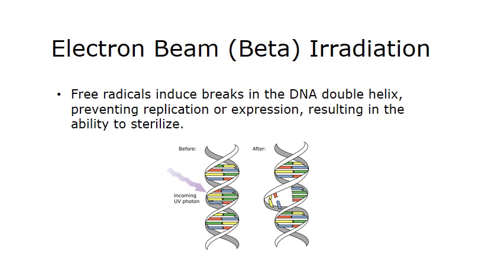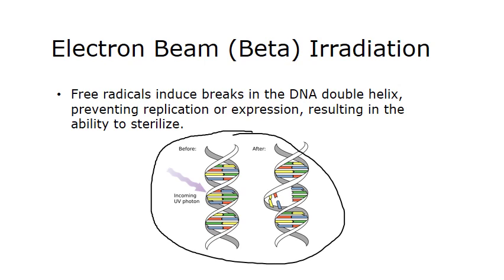Electron beam radiation is very efficient, but for polymer-based medical devices it is not always desirable because the electrons can damage the polymers. Free radicals work by inducing breaks in the DNA double helix. Here's a schematic showing DNA before and after electron exposure. Once a break is introduced into the DNA double helix of a living organism, that organism is no longer able to replicate or reproduce, and therefore it dies — leaving no living matter on the medical device.